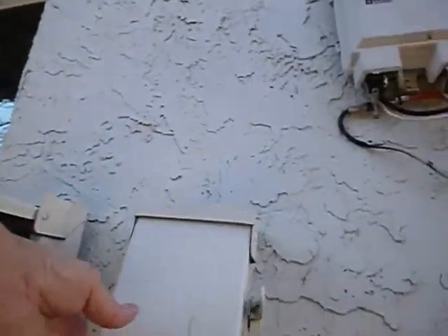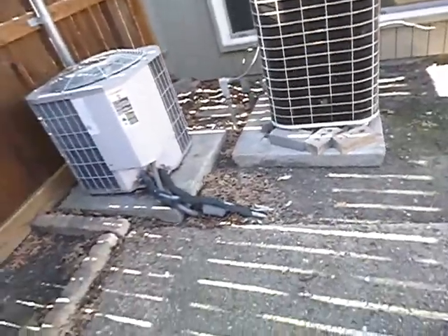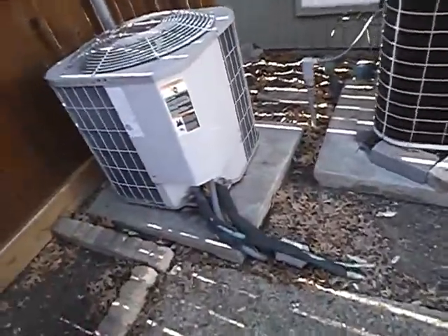The electric service disconnects are fine — they're over here on the wall. However, they should be sealed on three sides to help prevent moisture infiltration into the wall. The refrigerant lines — the low-pressure ones at least — should be insulated, and they were. But when they were installed, this insulation was acceptable; it no longer meets today's energy code, probably since around 2015. It would need to be a more rigid, protective cover.